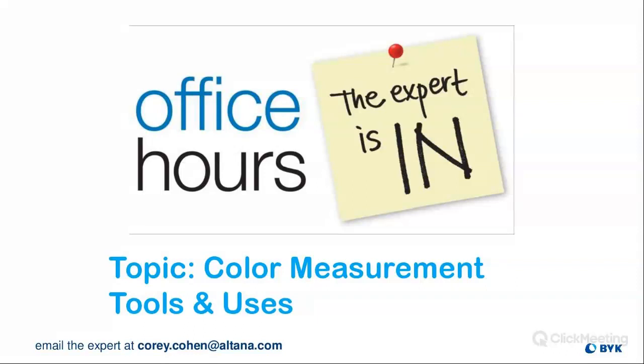The newer instruments actually will tell you whether to calibrate or not. It will ask you based on things like when it was last calibrated, or if there are changing temperature conditions, to perform a diagnosis, meaning a measurement of that calibration standard.